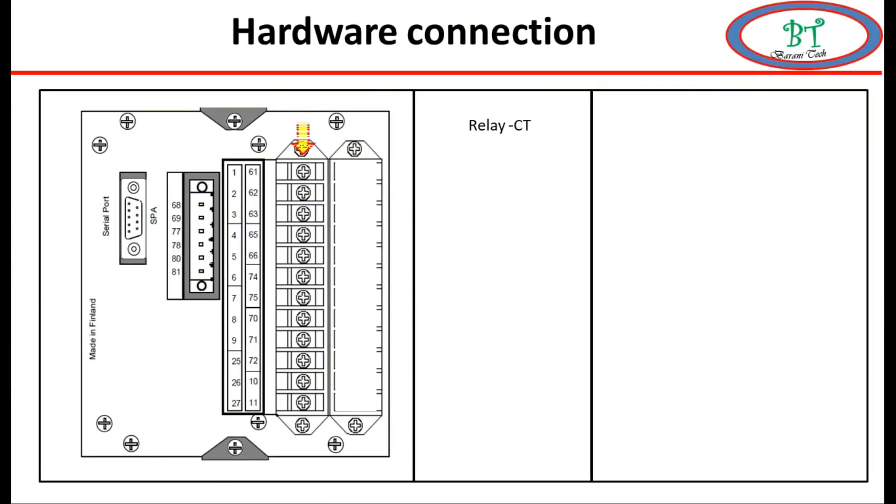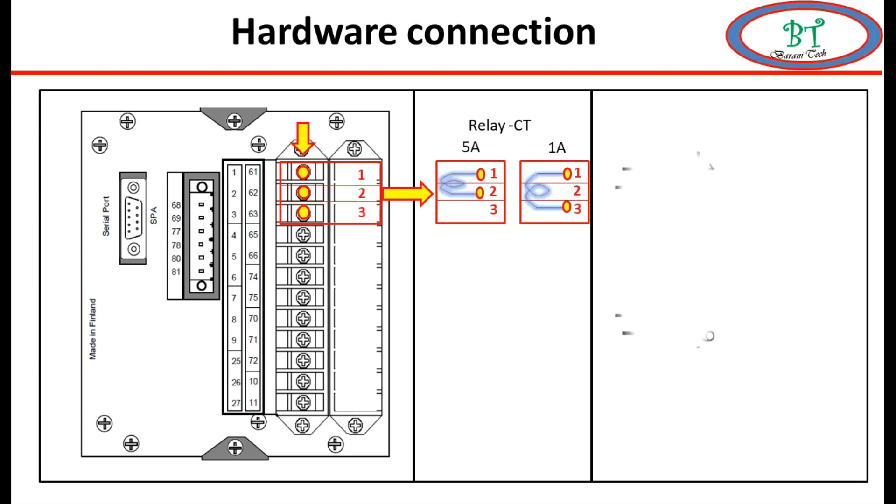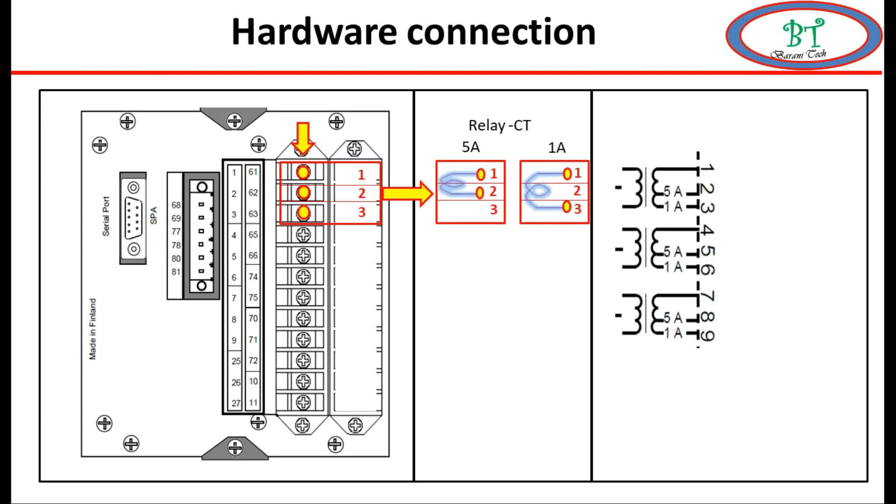Now we go to the second card. This card is fully an analog card, only used for sensing current from the CT secondary. Terminals 1, 2, 3 are the selection for phase CT. The connection using terminals 1 and 3 is used for 1 amp CT secondary from S1 and S2. If you want to use 5 amps, then you need to connect S1 and S2 to terminals 1 and 2. Similarly, terminals 4, 5, and 6 are for another phase CT, and 7, 8, 9 for another phase CT.